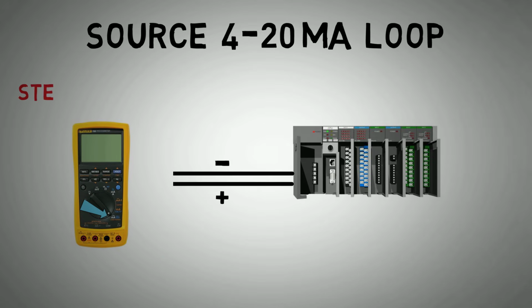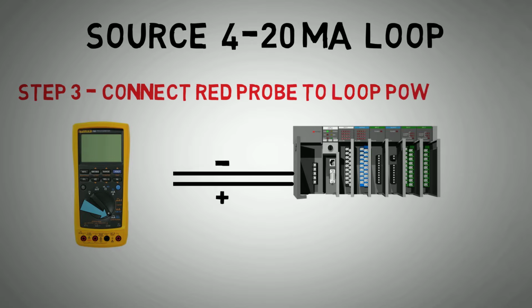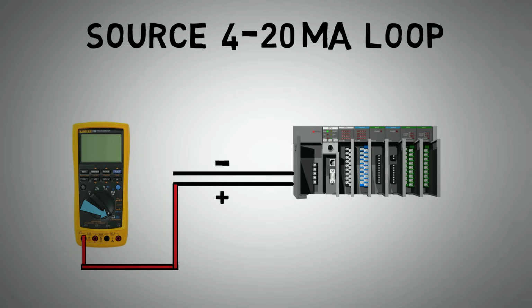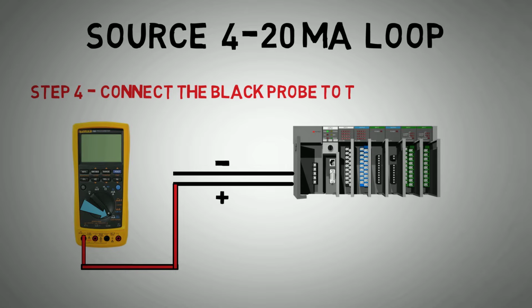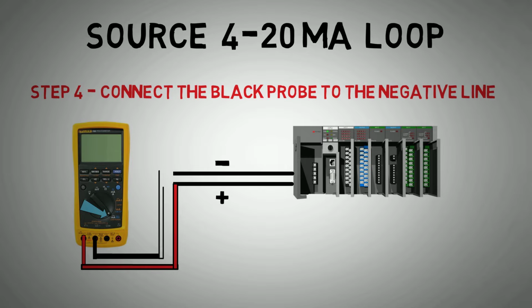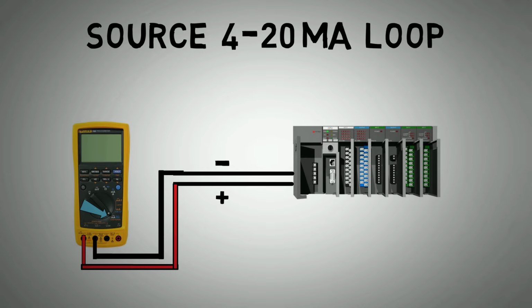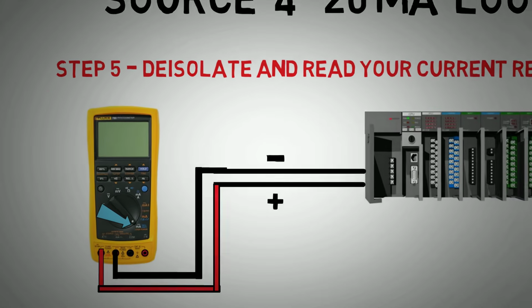Step 3. Connect the red probe to the left loop power port on the meter and connect to the positive wire going back to your input card. Step 4. Connect the black probe to the milliamp output port and the negative wire going back to your input card. Step 5. De-isolate the loop. Congratulations, you are now sourcing the loop and can change the current settings with the coarse and fine up and down arrows to step through different current values between 0 and 20 milliamps.